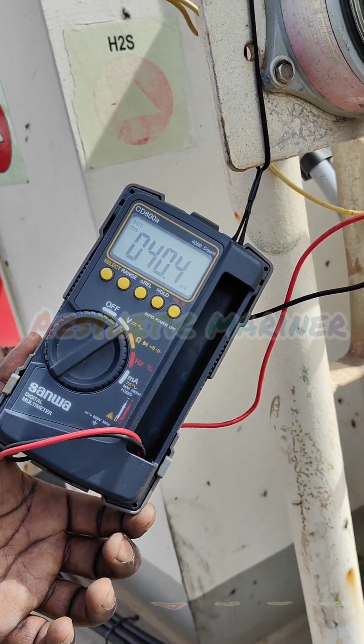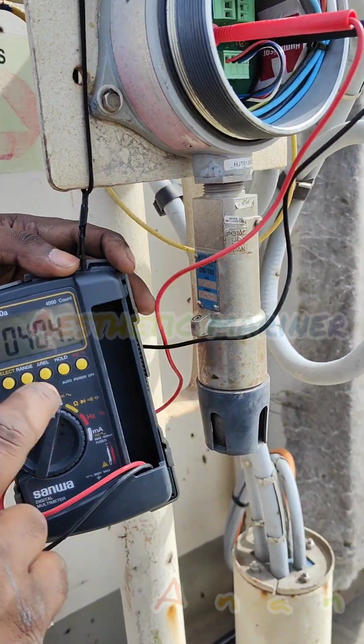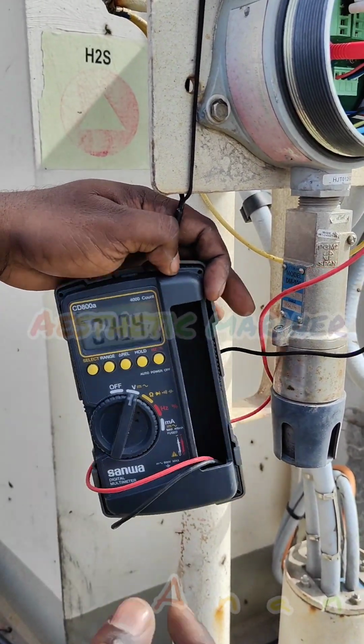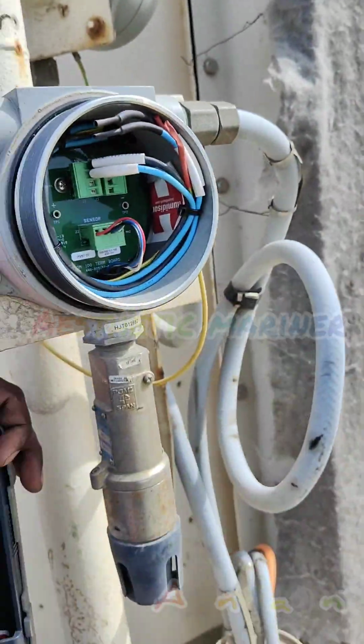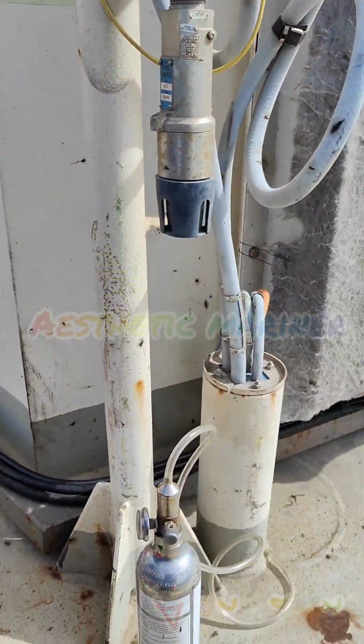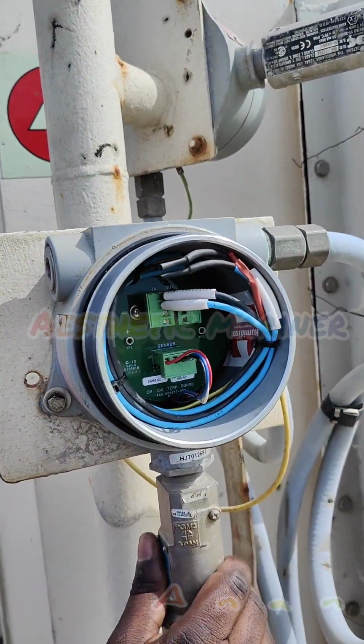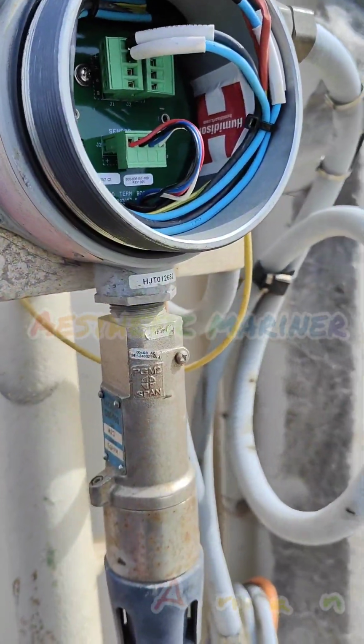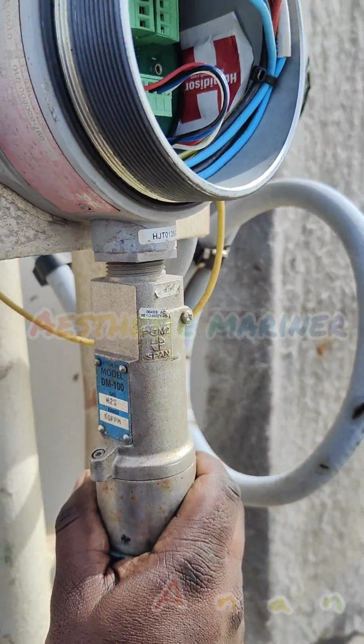Now it has reached 40.4 millivolt. Now we can remove our multimeter. The sensor is at 0 ppm now. This is it, the calibration of the Detcon DM100 model H2S sensor, without display type.